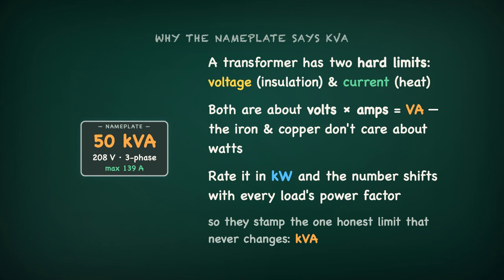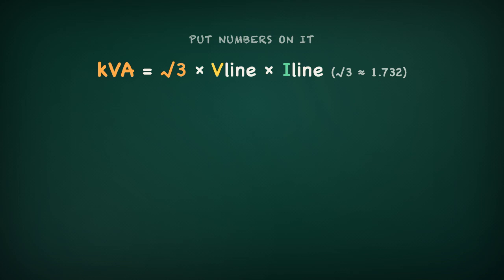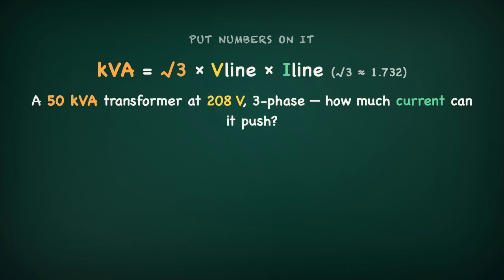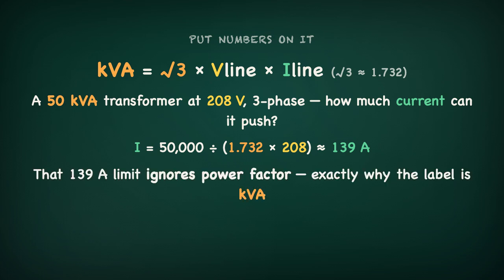So they stamp on the one honest limit that never changes. The kilovolt amps. Let's put numbers on it. For three phase, apparent power equals the square root of 3, about 1.732, times the line voltage times the line current. Take a 50 kilovolt amp transformer at 208 volts. How much current can it push? Rearrange. Current equals 50,000 volt amps divided by 1.732 times 208. That's about 139 amps. That current is the real limit, and it does not care about power factor, which is exactly why the label is in kilovolt amps.